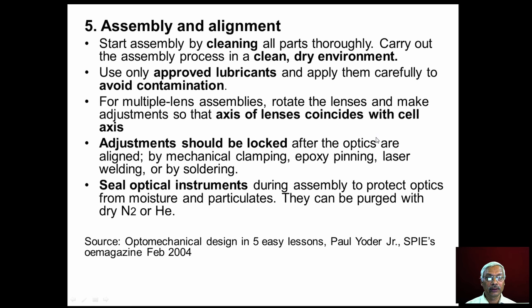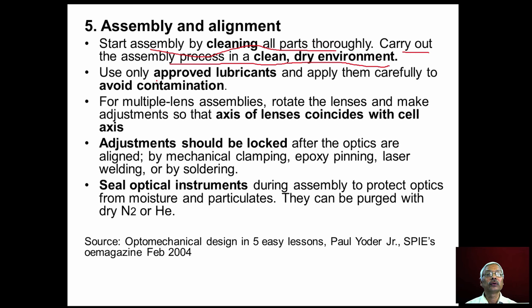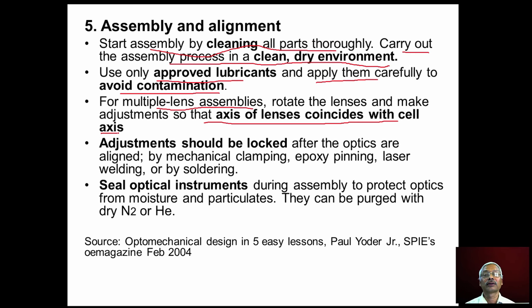The fifth important design decision concerns assembly and alignment of optics inside the mechanical structure. All optical and mechanical parts must be thoroughly cleaned, and assembly must be carried out in a clean and dry environment using approved lubricants applied carefully to avoid contamination. For multiple lens assemblies, lenses are rotated and adjusted until the axis of lenses coincides with the cell axis, using either a manual lens assembling process or automated alignment stations.